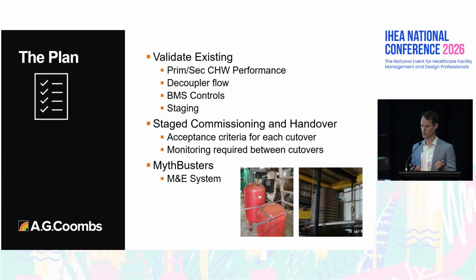When we got there, we had a closed tank and an open tank, both isolated, so we were scratching our heads. Apparently that was because there was a recent leak. What we found out was that this central plant is connected to another central plant on Block D, hydronically connected, and that's where the system expansion tanks were. So we validated the performance of those tanks to confirm, based on our height, we were okay.